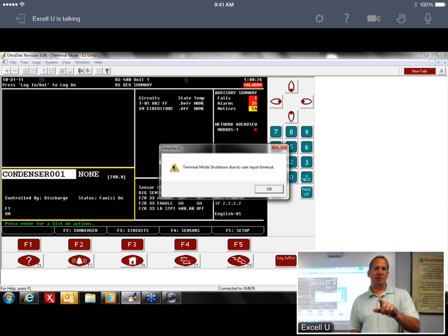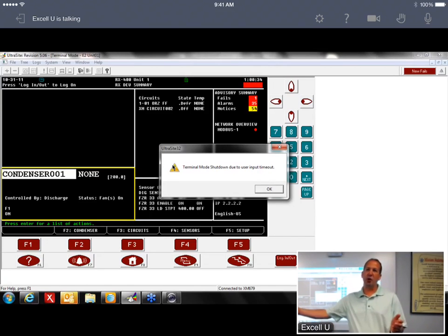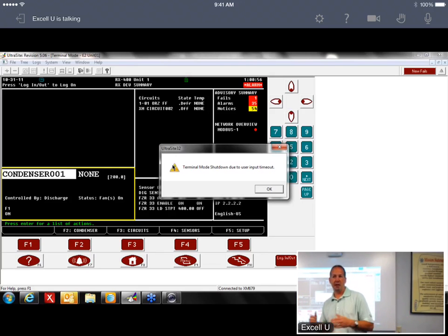Well, so they can't be on the same loop. I can't have Dixells and CCBs on the same one. What I was saying is you can reuse that CCB network cable if everything on that network is going to Dixell. But you can't mix CCB and Dixell on the same network loop, because they have different protocols. The old CCB's on IONet, the new Dixell's on Modbus, so they won't both talk on the same network. If you're going to have both, you'd have to run a new network for the Dixell.